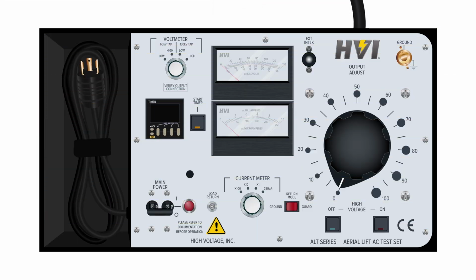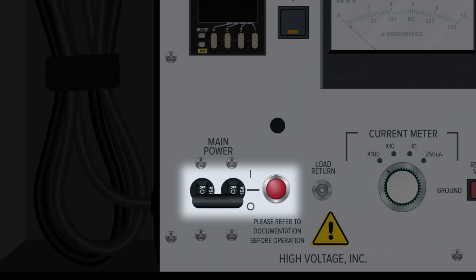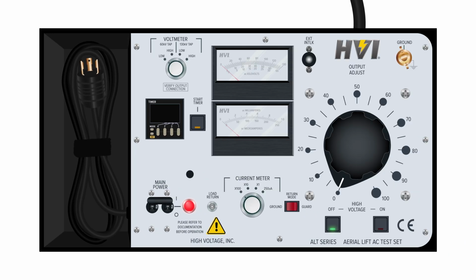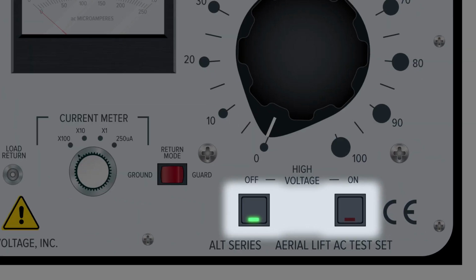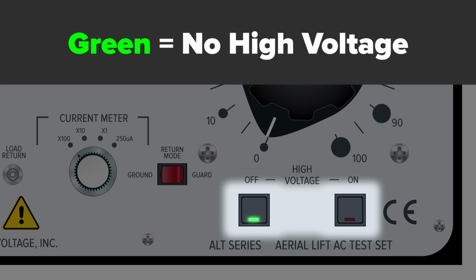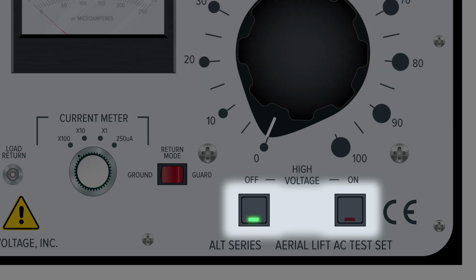The main power switch for the ALT series is located in the bottom of the panel. When turned on, the display light will illuminate in red. ALT series Hipots have on and off LED indicators for the high voltage circuit. When the device has the main power turned on, but the high voltage circuit is not energized, the display light for off will illuminate in green, meaning safe.